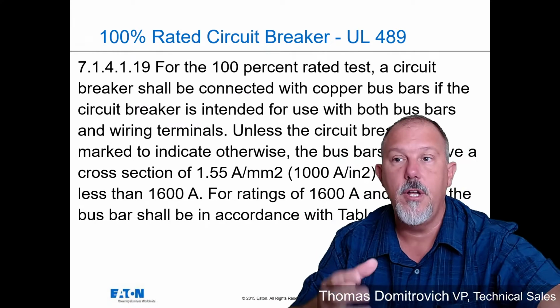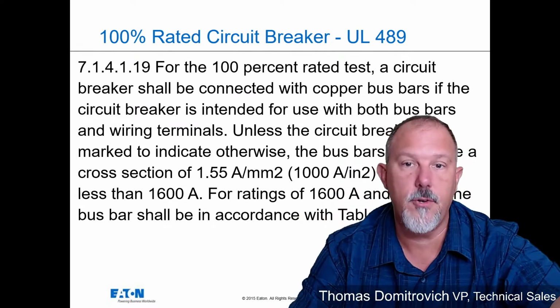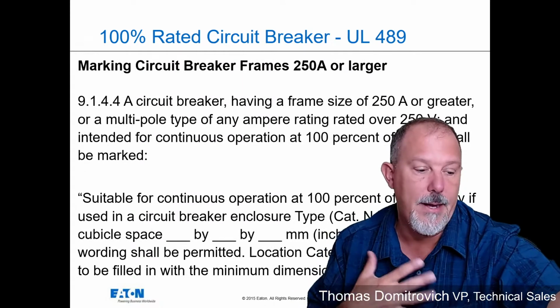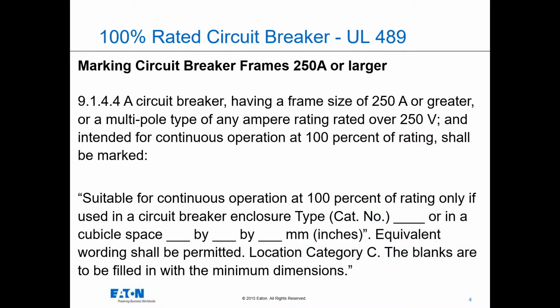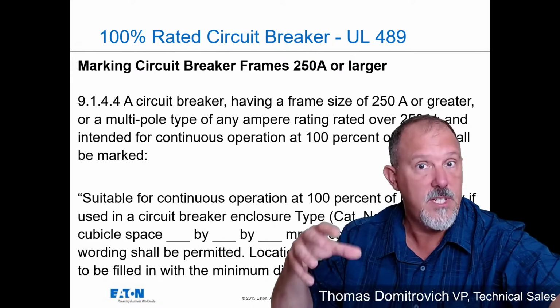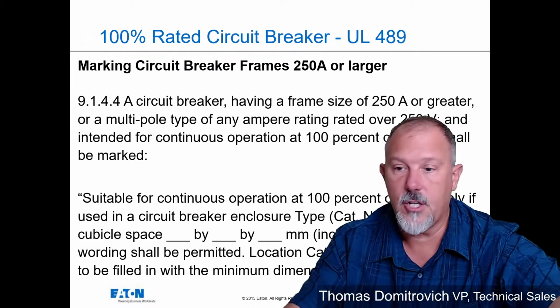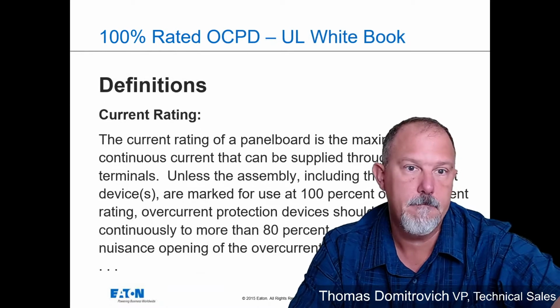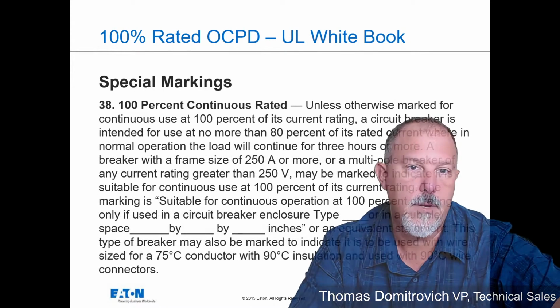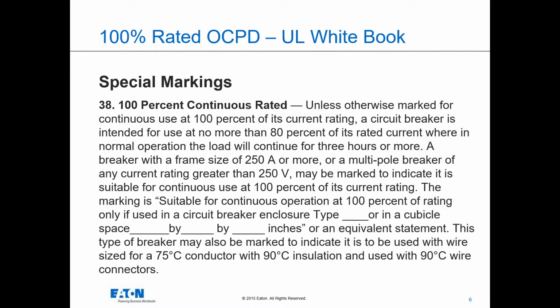So if you have an enclosure that has an aluminum bus, you are not going to have a 100% rated enclosure because it's all about heat. So a circuit breaker having a frame size of 250 or greater or a multi-pole type and intended for continuous operation shall be marked suitable for continuous operation, 100% of rating, only if used in a circuit breaker enclosure. And so they specify the enclosure or a cubicle space. Okay, so they're specifying this. Remember, this is very integrated with the enclosure and the copper and all of that stuff that you have going on inside of there. We know current rating. All right, so this is out of the UL White Book.